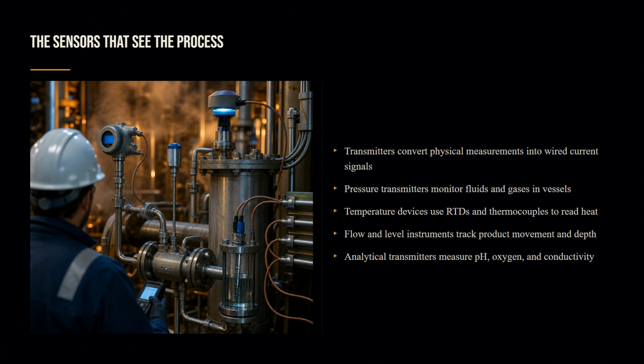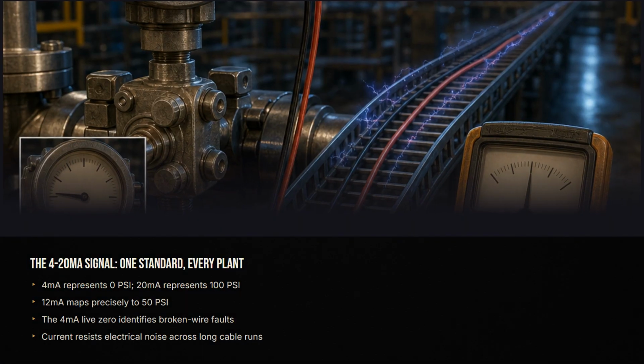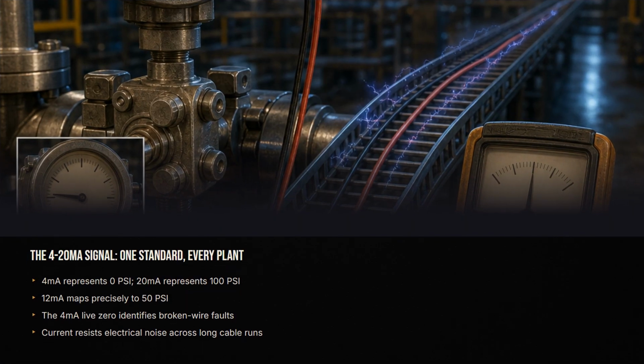The signal follows one universal standard: 4 to 20 milliamps. Take a pressure transmitter measuring 0 to 100 psi. At 4 milliamps, it reads 0 psi. At 20 milliamps, it reads 100 psi. At 12 milliamps, the pressure is exactly 50 psi.